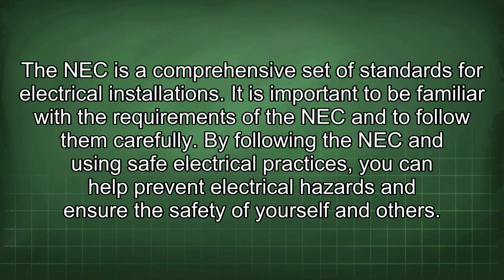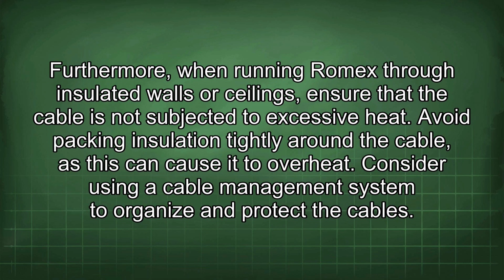The NEC is a comprehensive set of standards for electrical installations. It is important to be familiar with the requirements of the NEC and to follow them carefully. By following the NEC and using safe electrical practices, you can help prevent electrical hazards and ensure the safety of yourself and others. Furthermore, when running Romex through insulated walls or ceilings, ensure that the cable is not subjected to excessive heat. Avoid packing insulation tightly around the cable, as this can cause it to overheat.